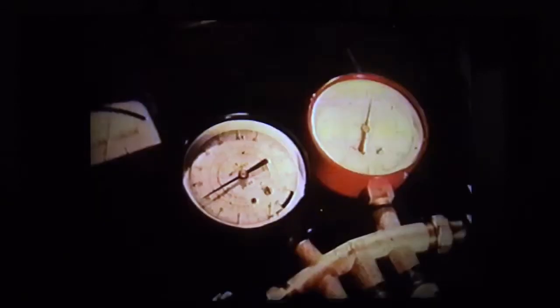Loosen the center hose fitting at the manifold and crack both manifold gauge valves for 10 seconds to purge air from the service hoses. Operate the engine at 1300 RPM for 5 to 10 minutes with doors open, vents closed, air conditioning set for maximum cooling, and the blower set on high speed.